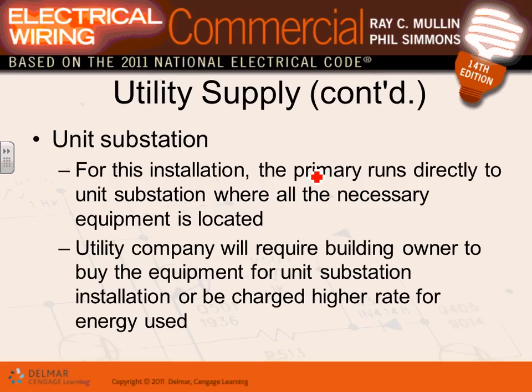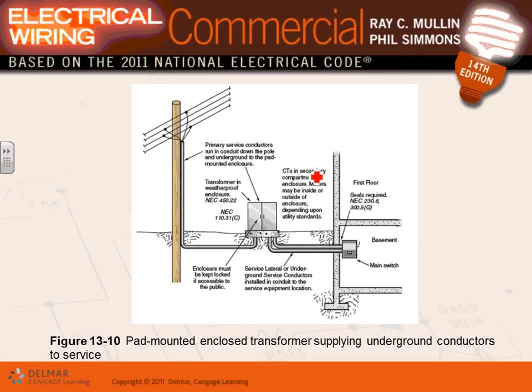We talked about the unit substation, guys, where they tie everything together. If you have a unit substation where they have the high voltage, low voltage, and a transformer all in one section. So typically, if it's provided by utilities, you have to pay for it. There's some arrangement. Here's one way of connection, guys. Look at this one. We're bringing the power from overhead into underground. We came to the high voltage section. We transform it. We came back into my disconnect means. That's a typical commercial preferred pad mounted transformer. A lot of engineers prefer this way.